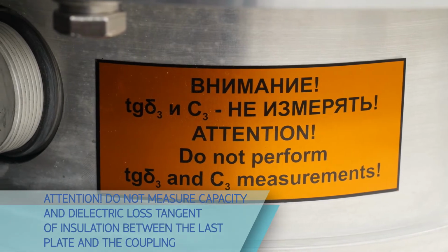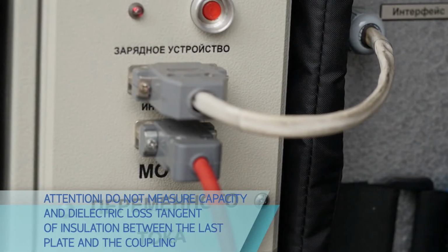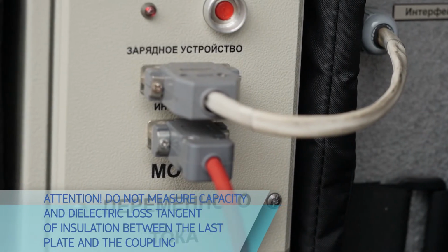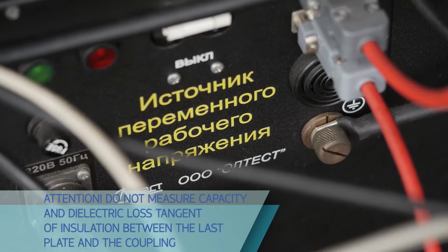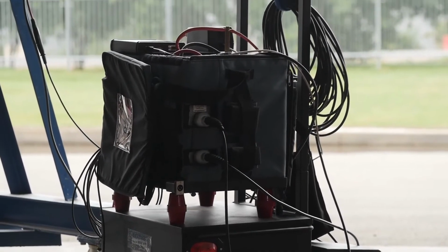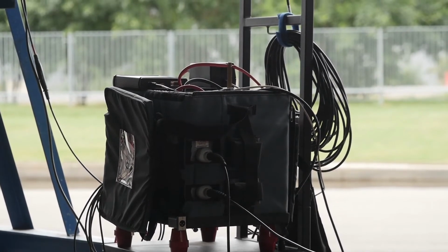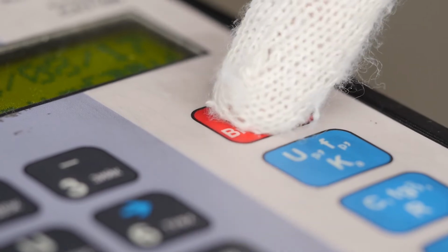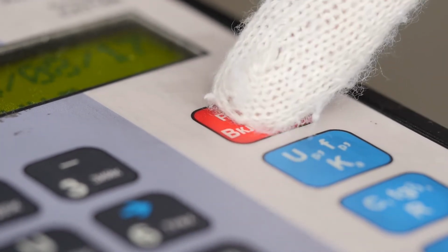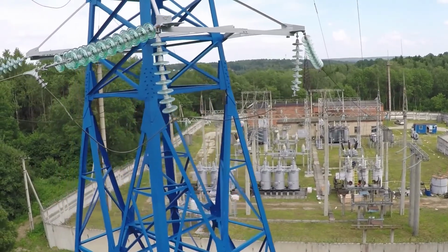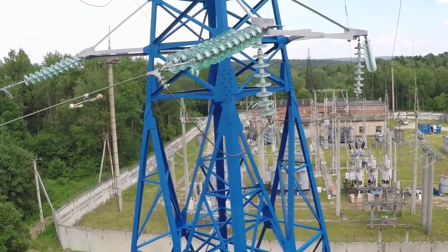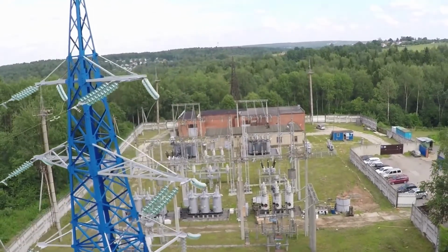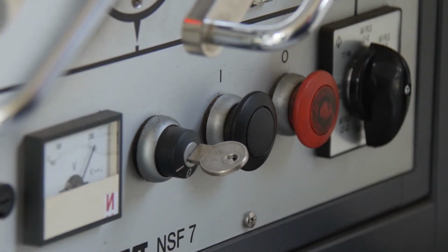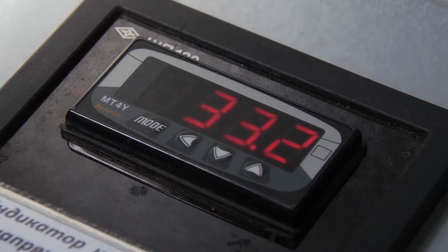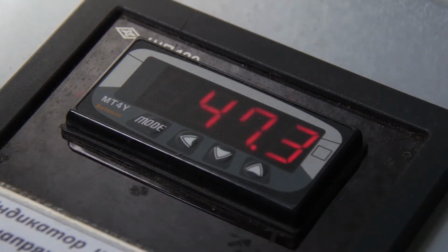Bushing measurements require certain experience in handling measurement tooling, configuration, and interpretation of measurement results. Partially, it depends on the fact that capacity values are relatively small and may be distorted even under the effect of environmental spatial factors, as well as the bushing position inside the transformer may also impact measurement results after installation. Measurement results of the dielectric loss tangent are also dependent on humidity, weather conditions, and other factors. Correct measurements and assessment of results allow ensuring efficient operation of the bushing within its entire service life.